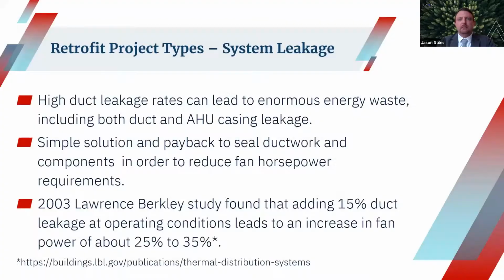Next we look at system leakage as a whole—not just ductwork, but air handling units and terminal devices too. Once leakage reaches a certain range, there's a lot of potential energy savings—think of it as money seeping out through the holes. As a rule of thumb, we typically see around $750 per horsepower running continuously. Applied to a large facility with five or six major air handlers, you can see how that cost adds up quickly.